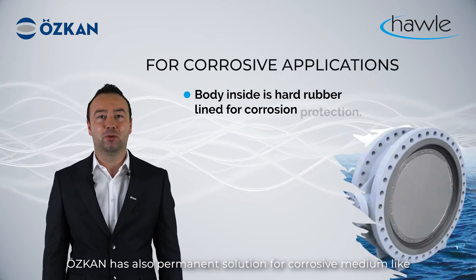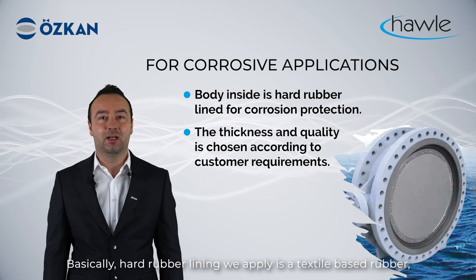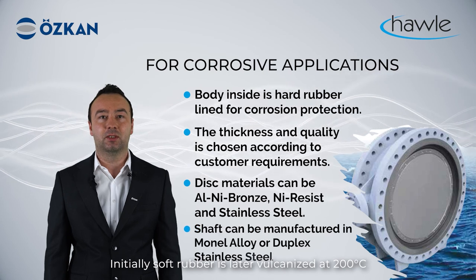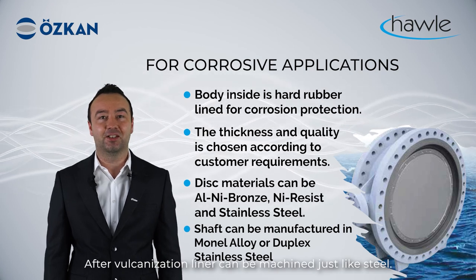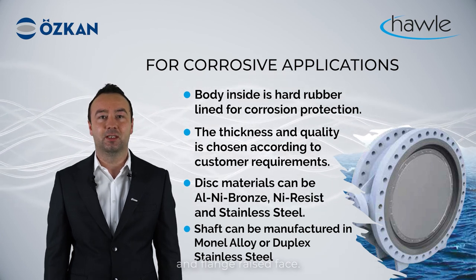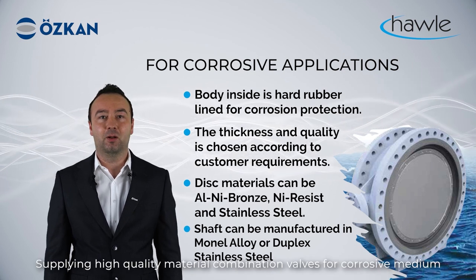ÖZKAN also has permanent solutions for corrosive mediums such as sea water and brackish water, with many references in this application field. The hard rubber lining applied is a textile-based rubber which is glued onto the internal surface of the valve. Initially soft rubber is later vulcanized at 200 degrees Celsius with 25 bar pressure in an autoclave. After vulcanization, the liner can be machined like steel, giving the valve a perfect finish in seat bearings and the flanged raised face. The liner material used is ebonite for sea water applications. A version suitable for potable water use is also available. For corrosive mediums, high-quality materials such as super duplex and nickel resist are also available as options.